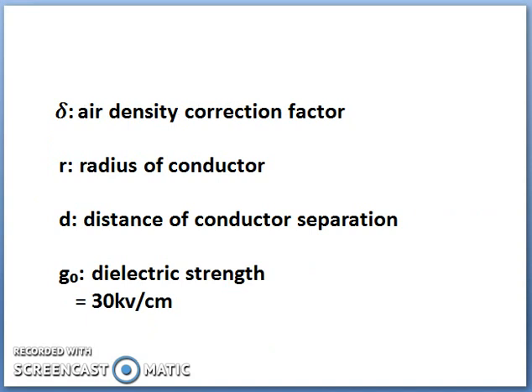Delta is the air density correction factor. R is the radius of the conductor and D is the distance between the two conductors. G₀ is the dielectric strength, which equals 30 kilovolts per centimetre when the temperature is at 25 degrees centigrade and the air pressure is at 76 centimetres of mercury.